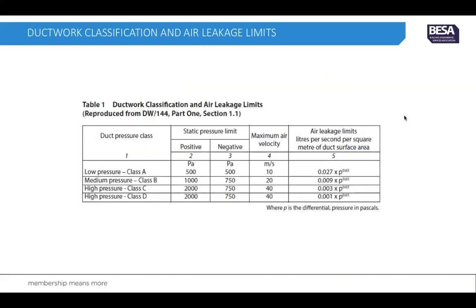The ductwork classifications and air leakage limits are as follows: Class A — positive pressure 500 pascals, negative pressure 500 pascals; Class B medium pressure — positive 1000 pascals, negative 750 pascals; Class C high pressure — 2000 pascals positive, 750 pascals negative; and Class D high pressure — also 2000 pascals but with a lower leakage rate.